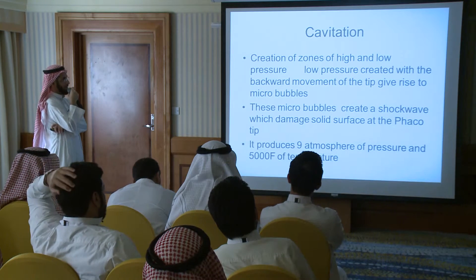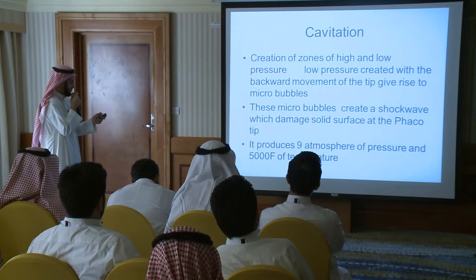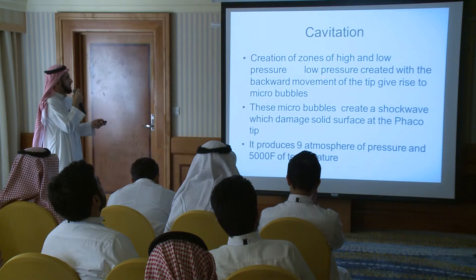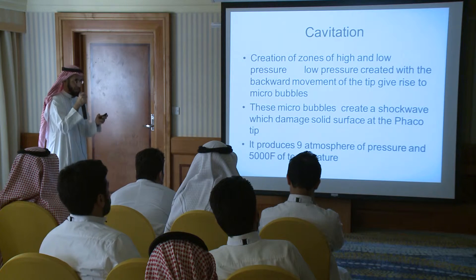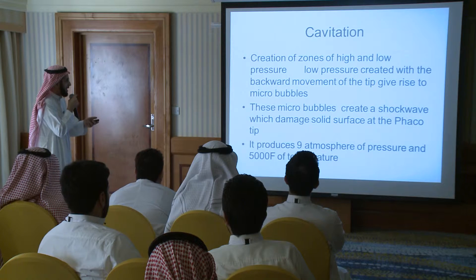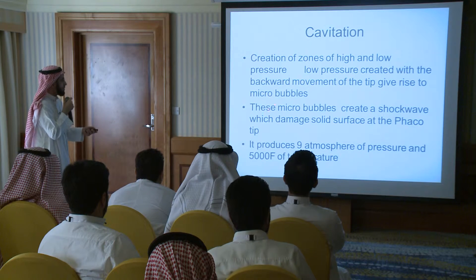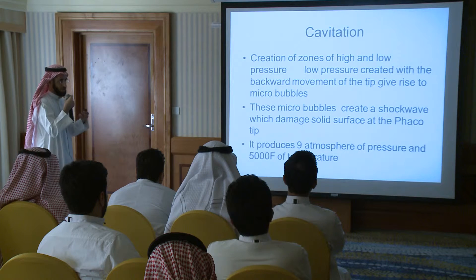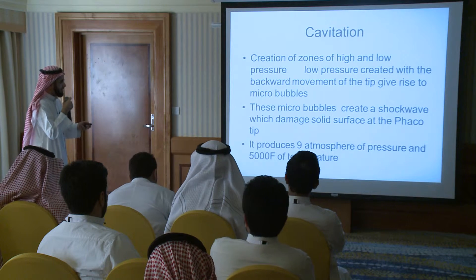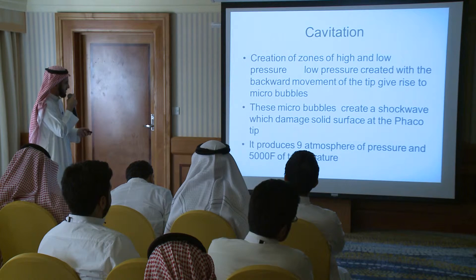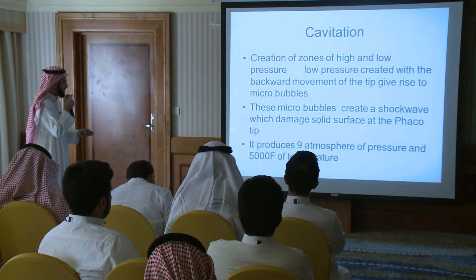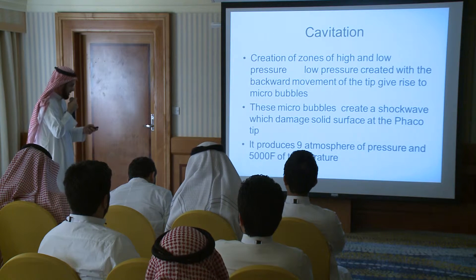We also emulsify the nucleus through what we call cavitation — the creation of zones of high and low pressure. The low pressure is created by the backward movement of the tip of the needle. As it moves backward, it creates a negative pressure, which creates microbubbles. These microbubbles create shock waves that damage solid surfaces near the Phaco tip and cause emulsification of the lens. Most of the time we don't want to go to cavitation because it releases a lot of energy.